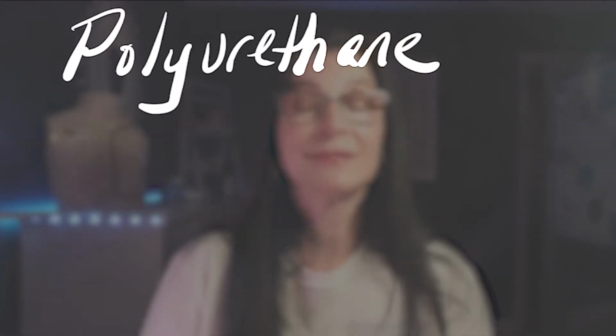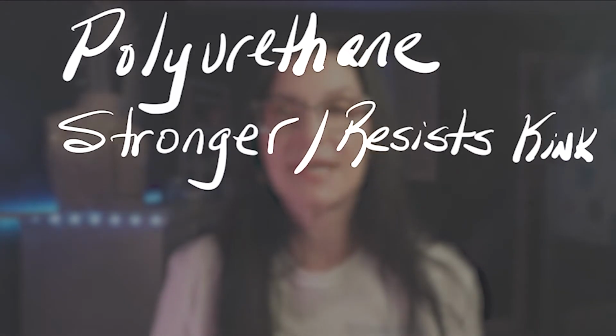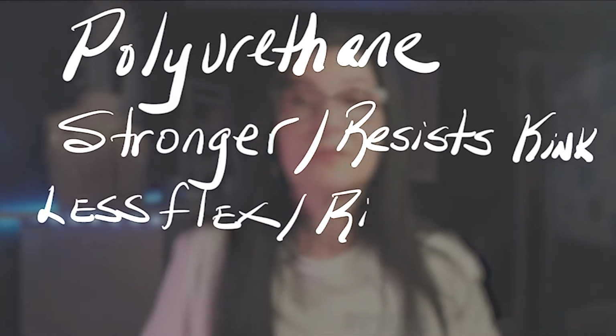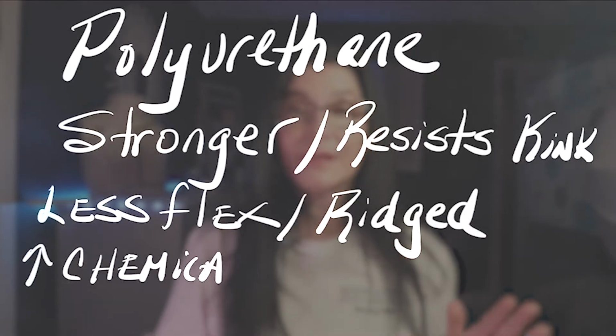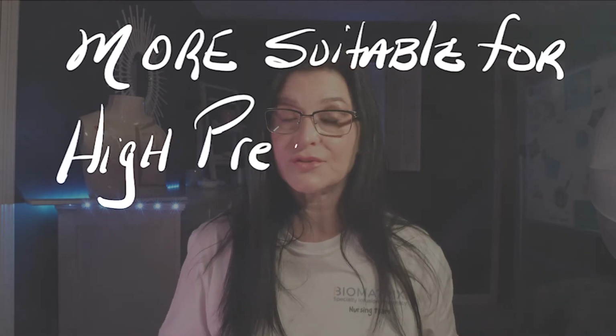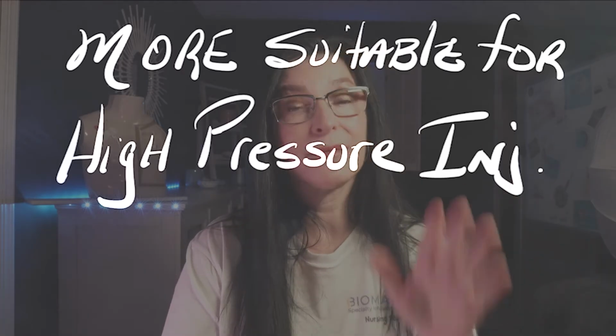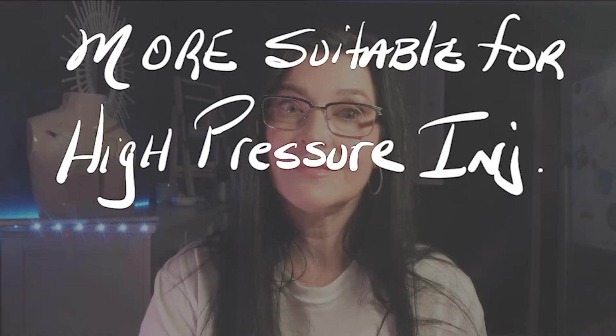Polyurethane catheters, on the other hand, tend to be stronger and more resistant to kinking, but this quality also makes them less flexible, so the catheter is a bit more rigid. They're also chemically resistant, so they don't wear down as easily with harsh drugs as silicone does. And then the last distinguishing characteristic here is that they're suitable for high pressure injections. And I'll explain what that means in a sec. But because of all of these qualities, they do have a drawback, which is that they can be more prone to causing clots.